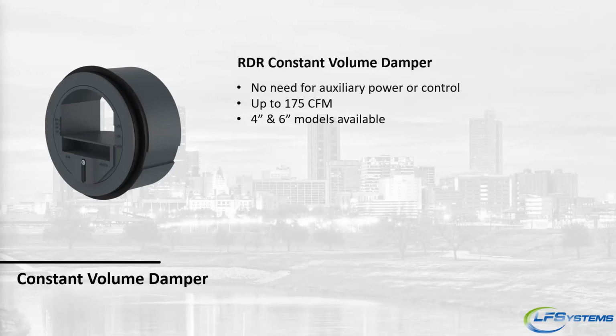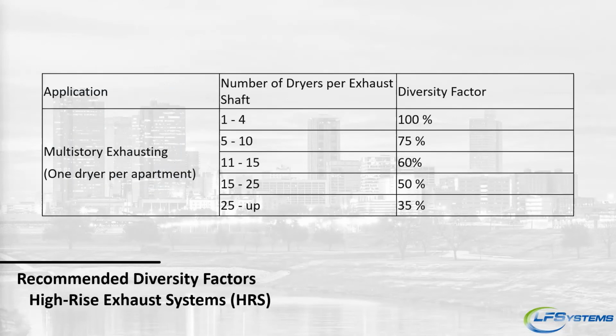So the other thing we look at when sizing our high-rise exhaust is diversity. Depending on the number of dryers or hoods per floor, or I should say per shaft, we will determine that, in most cases, if you have 20 dryers going into a single shaft, the chances of more than 10 of those working at once are pretty slim.